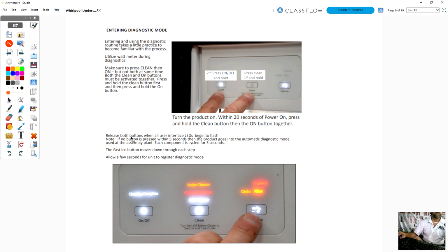Once you're in diagnostics, all the LEDs will begin to flash. So if you see this, all these LEDs flash. The reason why they do that, one, is to tell you you're in diagnostic. Two, in case any of the LEDs on the board are not working, this is a test to light them all up. If you see one that's not working, then your user interface that has these lights on it might be defective.